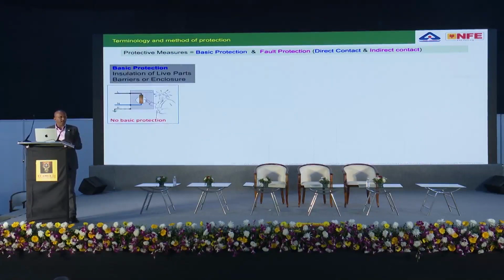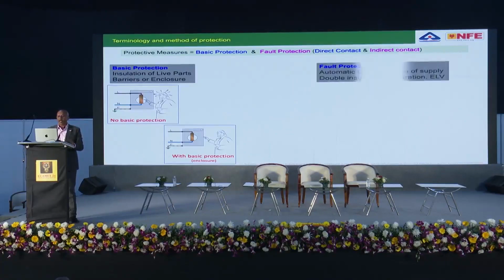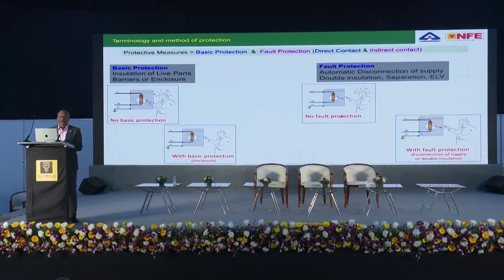The first one, what you are seeing, has no basic protection, meaning anybody can touch a live part and get electrocuted. The idea of basic protection is you put live parts inside an enclosure. As a result, nobody touches the live part directly. You get basic protection. This is one idea, and like that, several ideas are there. Then if there is a fault in that particular panel board, for example, the person gets shocked. What to do? Implement a fault protective measure.